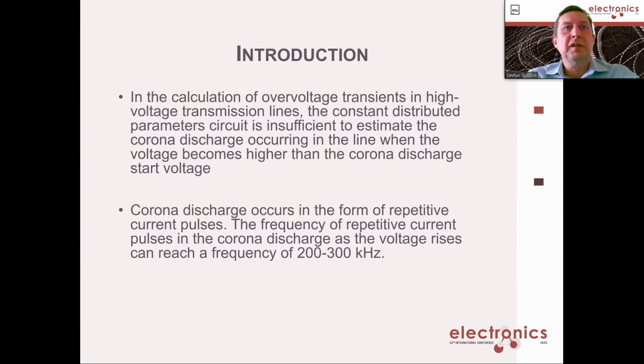The range of signals or measurements we use for detection of corona, the range of frequencies of the corona discharge, is from 200 to 300 kilohertz.